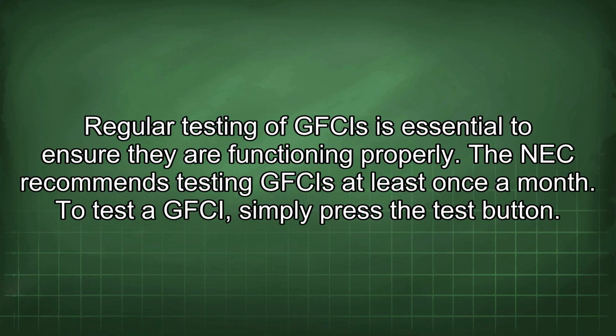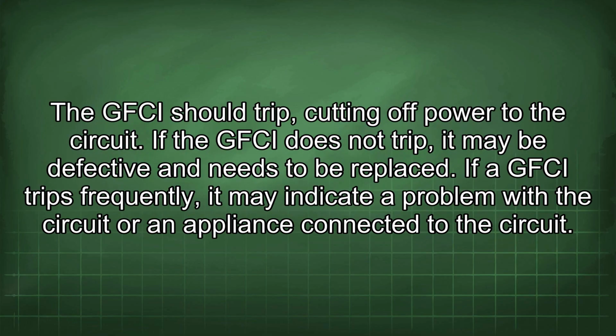Regular testing of GFCIs is essential to ensure they are functioning properly. The NEC recommends testing GFCIs at least once a month. To test a GFCI, simply press the test button. The GFCI should trip, cutting off power to the circuit. If the GFCI does not trip, it may be defective and needs to be replaced.